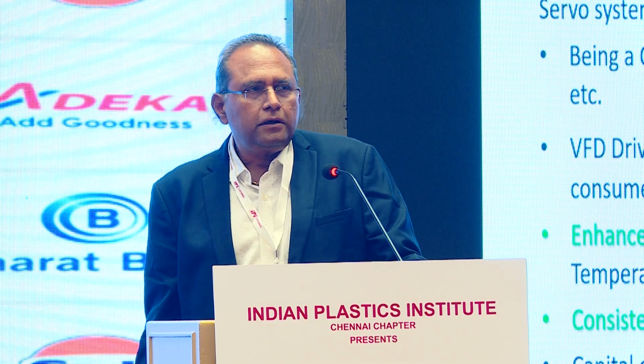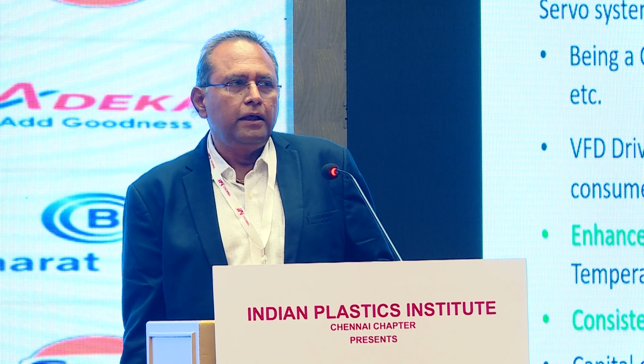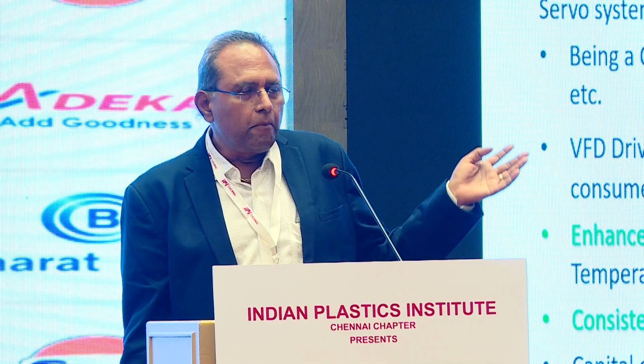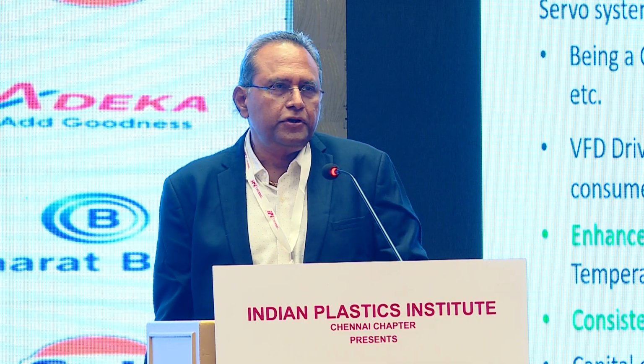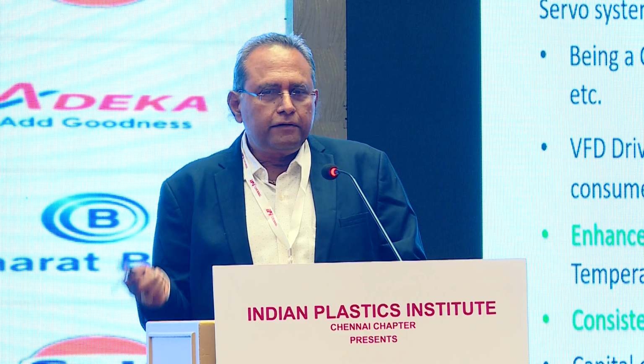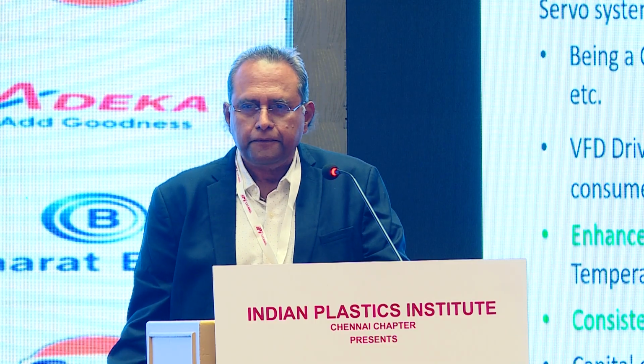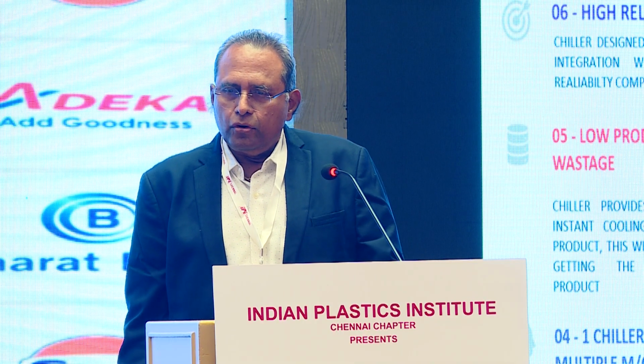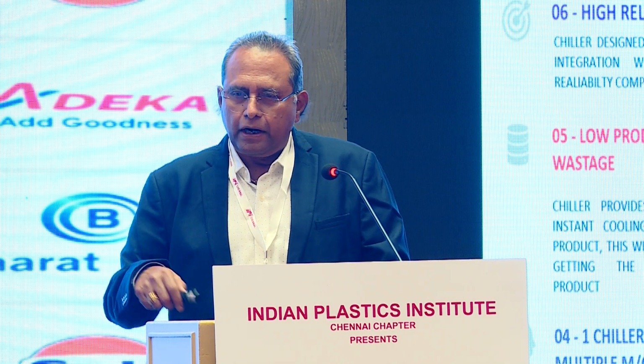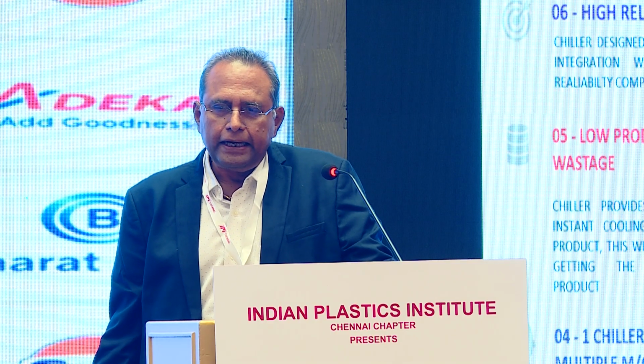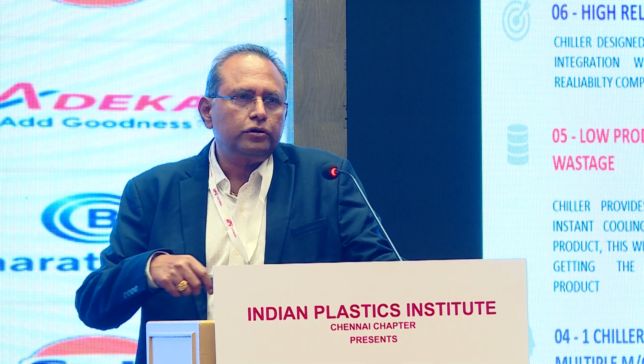And the capital cost also can be optimized by avoiding remote cooling towers, complicated piping, and distribution to various machines. All those things can be avoided, so that a single chill water can be used for both mold cooling as well as hydraulic power pack cooling. So this gives the benefits of the inverter based chiller for molding application. So low product cycle time because you can run at accurate temperature, better power saving, wide operating range, highly reliable, and you can use a common chiller for multiple machines.